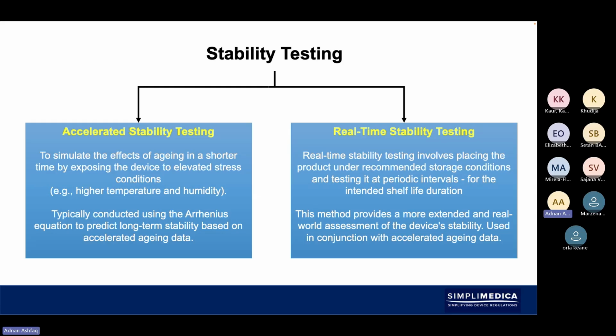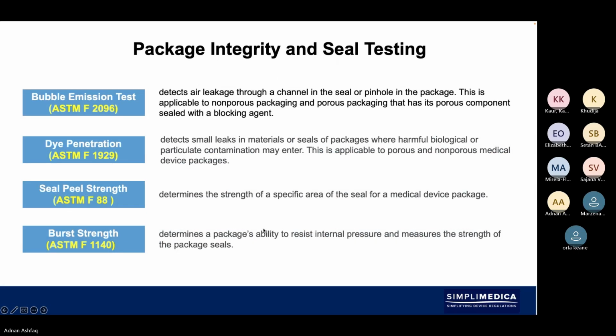intervals. But then also you can do an accelerated stability test, which would then, using a formula, you can accelerate that 5 years to several months. So you would also then do accelerated stability testing. As I said, if you've got a sterile device, even non-sterile device, this is actually good practice to do, just to check to see if there's any bubble emission, dye penetration, seal peel, strength test, and burst strength.